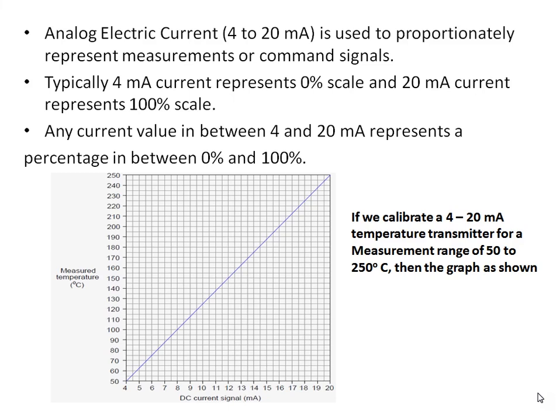Any current value between 4 and 20 mA represents a percentage between 0 and 100%. If we calibrate a 4 to 20 mA temperature transmitter for a measurement range of 50 to 250 degrees centigrade, then the graph is as shown — with 4 to 20 mA on the x-axis and 50 to 250 degrees centigrade on the y-axis. 4 to 20 mA is a commonly used industry standard for measuring and transmitting the process variable to a remote location.